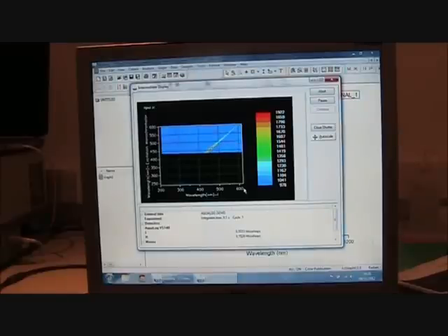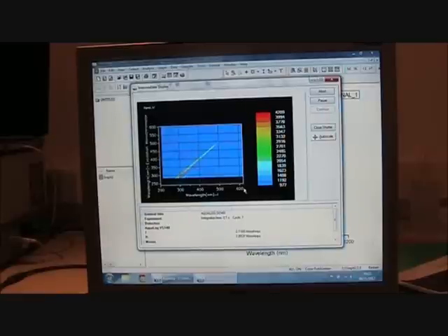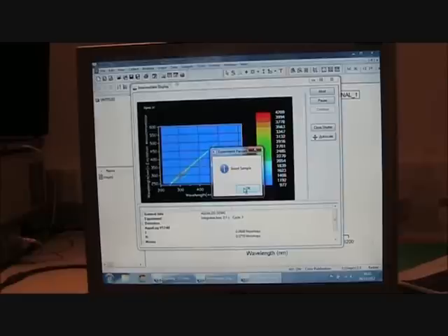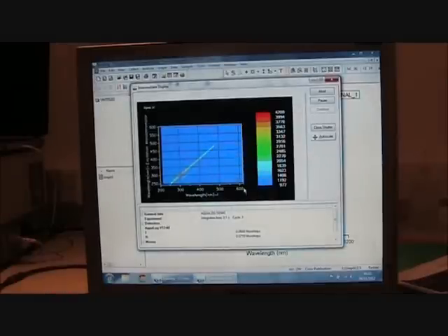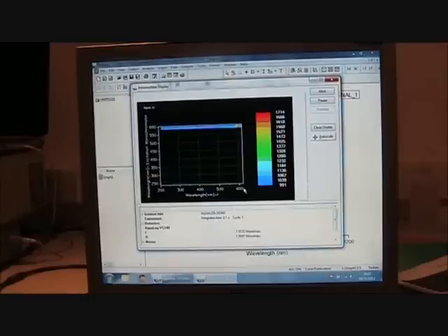The blank can be run for each sample, or this blank data can be used as the reference for all subsequent samples, so saving even more time. Now we remove the blank and put in the sample. You will note that the excitation goes from the higher to lower wavelengths to minimise any possible effect of radiation damage.